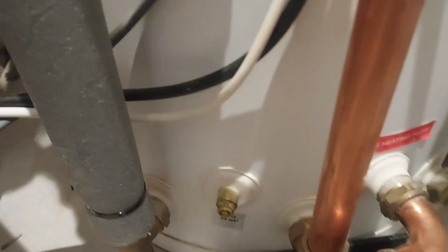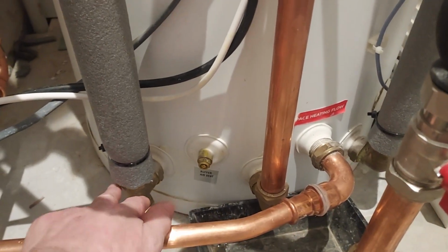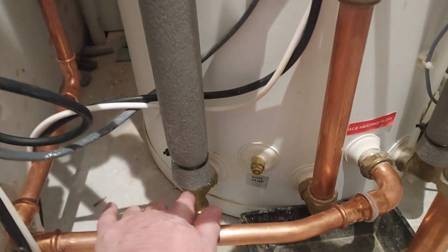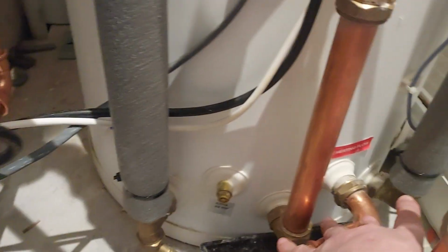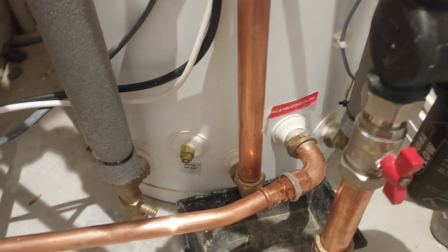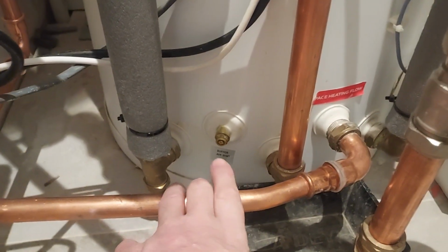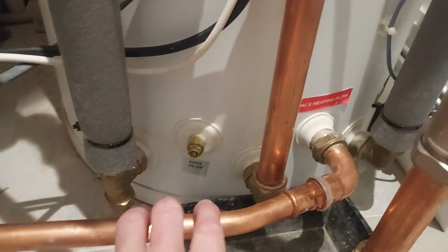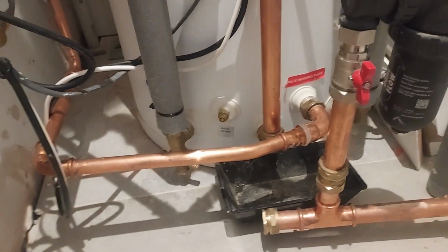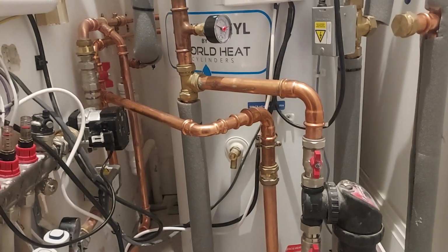So unless these have got pipes into the cylinder, look, this is our system flow and return, that's our boiler inlet, and that's the, not boiler, sorry, the heat pump return, that's our heat pump flow. So these have got to pass across these two. Yeah, and the return for the flow out to the system and the flow in from the heat pump are right next to each other. Shouldn't be happening, something strange going on there. But anyway, we'll see if we can get to the bottom of that.